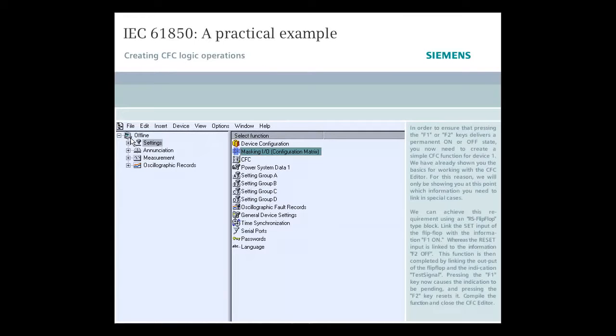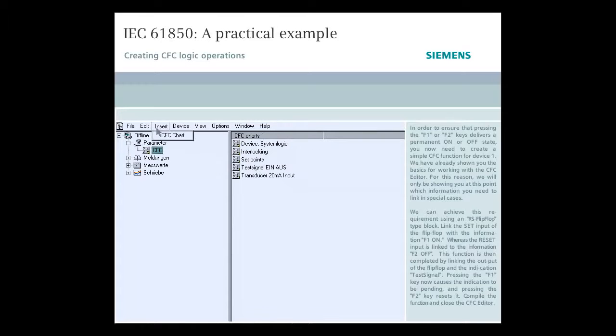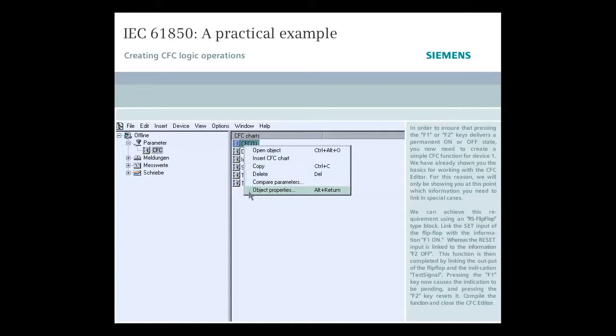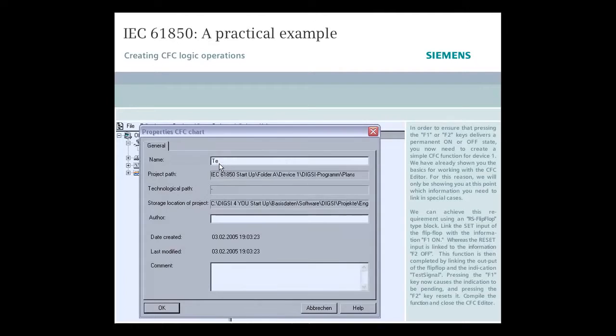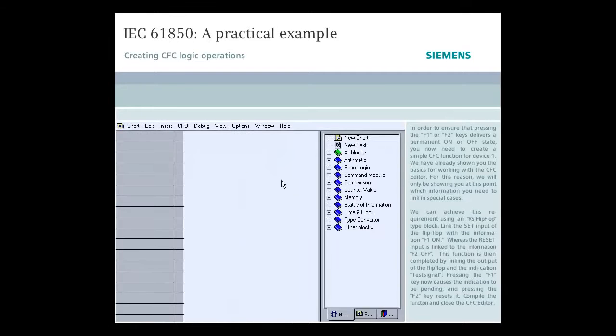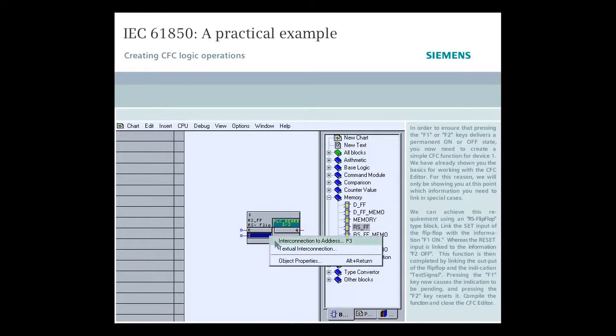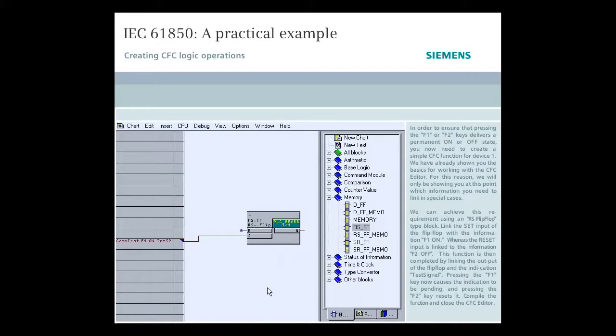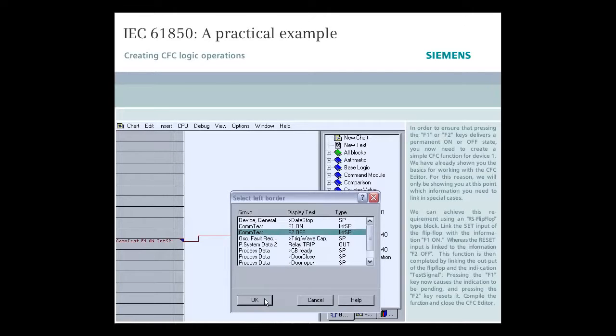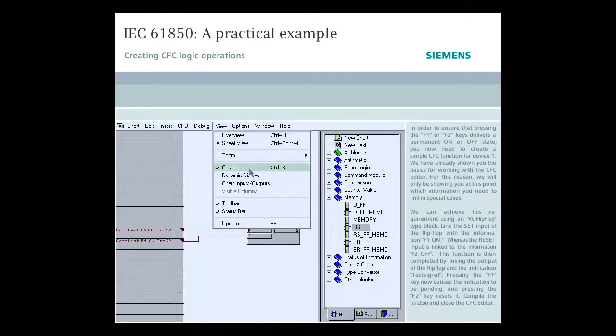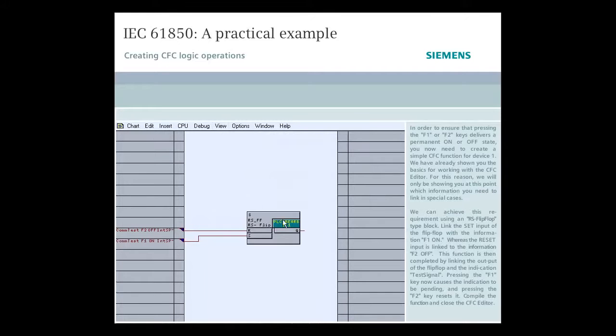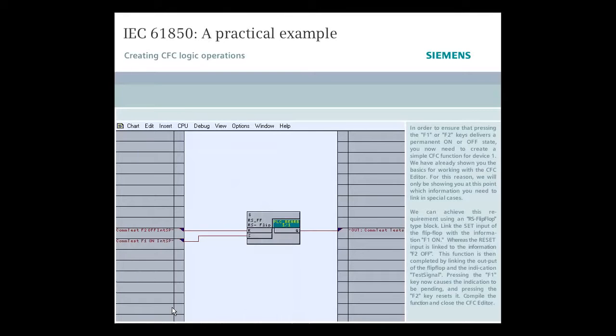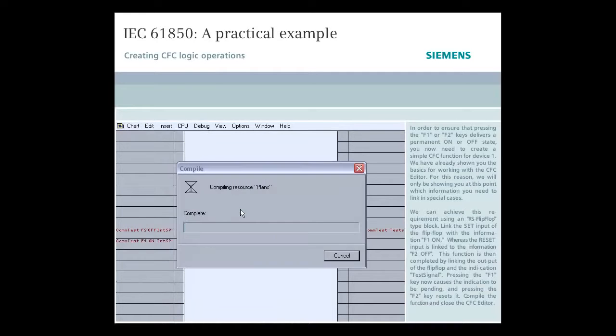In order to ensure that pressing the F1 or F2 keys delivers a permanent ON or OFF state, you now need to create a simple CFC function for device 1. We have already shown you the basics for working with a CFC editor. For this reason, we will only be showing you at this point which information you need to link in special cases. We can achieve this requirement using an RS flip-flop type block. Link the set input of the flip-flop with the information F1 ON, whereas the RESET input is linked to the information F2 OFF. This function is then completed by linking the output of the flip-flop and the indication TEST signal. Pressing the F1 key now causes the indication to be pending and pressing the F2 key resets it. Compile the function and close the CFC editor.